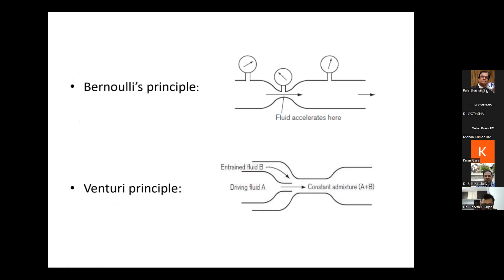Sir has already explained Bernoulli's and Venturi's principle. So what happens here? The size of the constriction is very important. If the constriction is smaller, the velocity of the gas flow is higher and the air entrainment will be more, because the pressure drop at the sides will be greater and more air is entrained. If the constriction is big, the pressure drop will be less, so less air is entrained and less oxygen is diluted, and a higher FiO2 will be delivered to the patient.